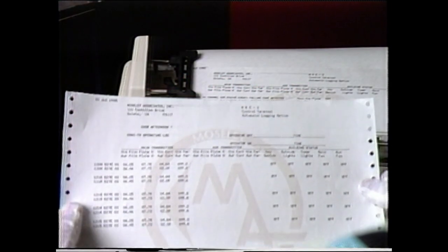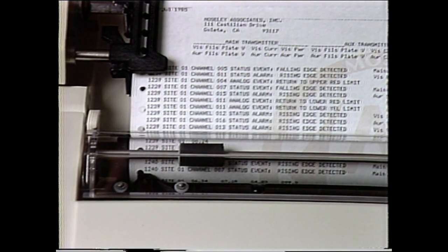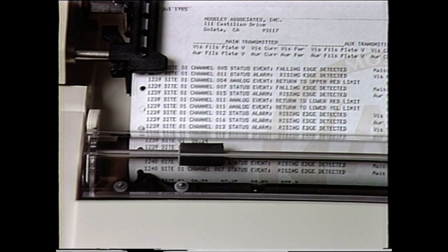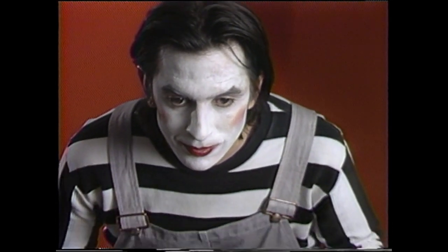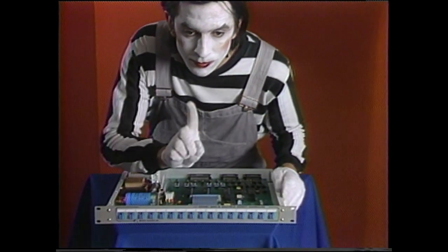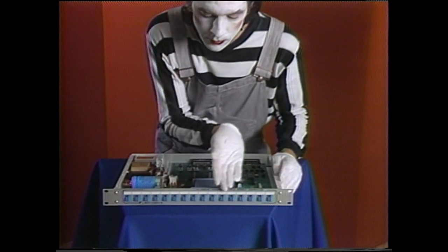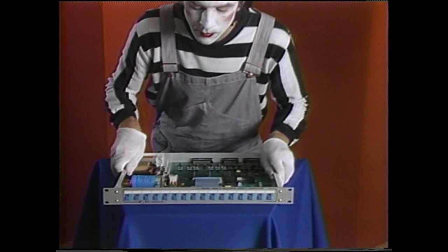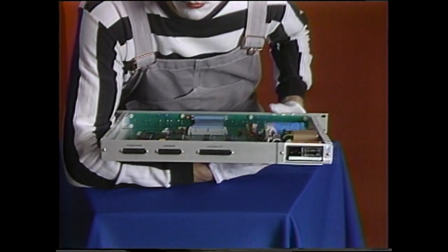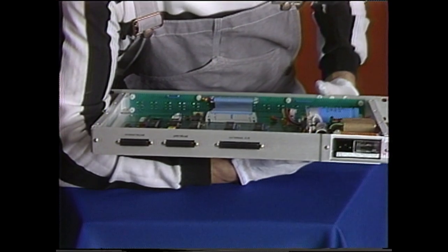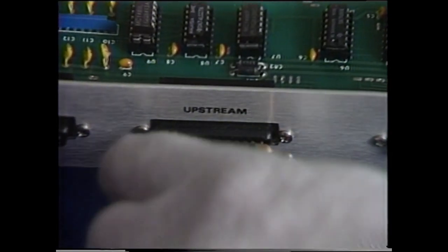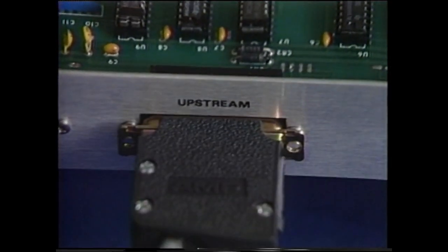The automatic logger produces a page containing the following parts: a header of user program text, time of day, selected logger channels recorded on a time basis, and alarms. The multiple direct command panel allows one button to select site, channel, and function. A tallyback confirms that the command has been accepted. Button contacts and tallyback drive are accessible from the rear panel. Up to 13 multiple direct command units may be interconnected to provide up to 208 command channels.